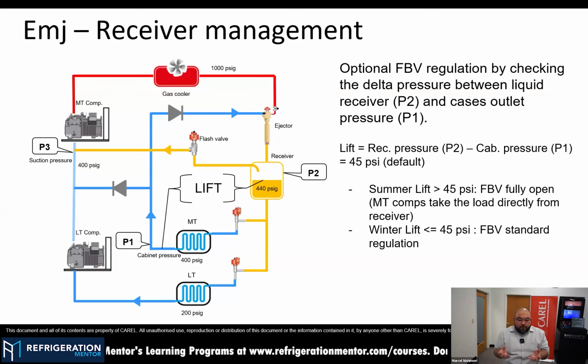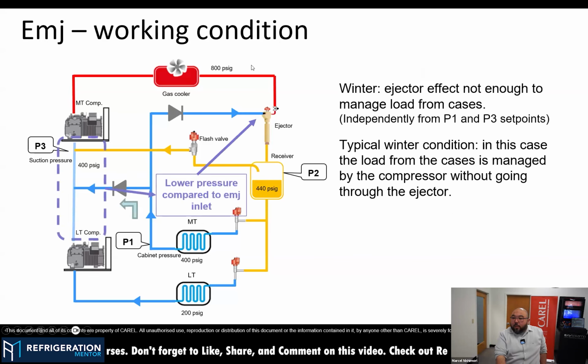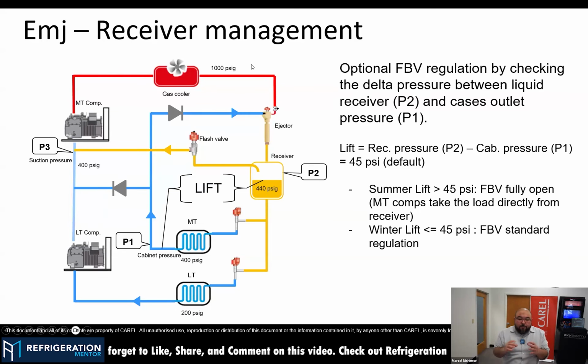So what can we do to improve the efficiency? Ejectors have a characteristic: the pressure increase from the cabinets to the liquid receiver, we call it lift. So the pressure that we are gaining with the ejector effect, we call lift. And we have a very curious behavior: the more lift I gain, so increasing pressure again, the lower the mass flow I have. So we need to play on this with design, basically, to make sure that we have enough flow going through the ejector and that we gain the maximum lift, so the maximum pressure increase that we can with the ejector effect.